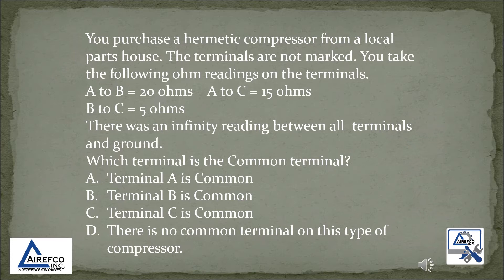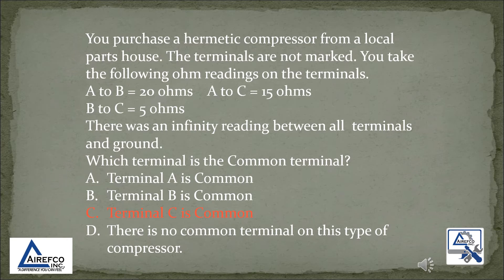You take the following ohm readings on the terminals: A to B is 20 ohms, A to C is 15 ohms, B to C is 5 ohms. There was an infinity reading between all terminals and ground. Which terminal is the common terminal?